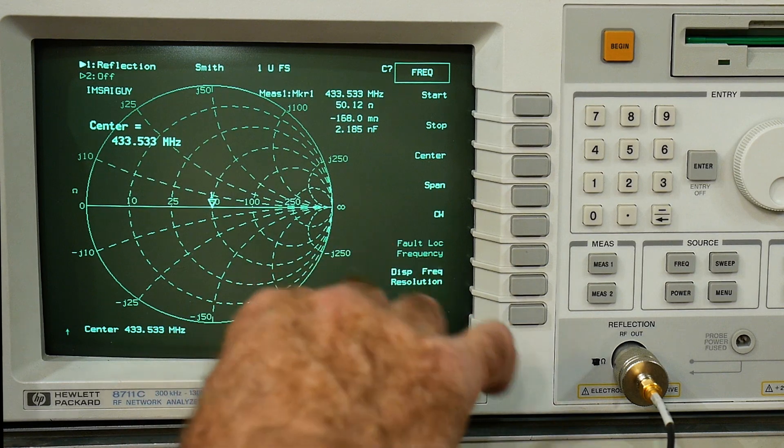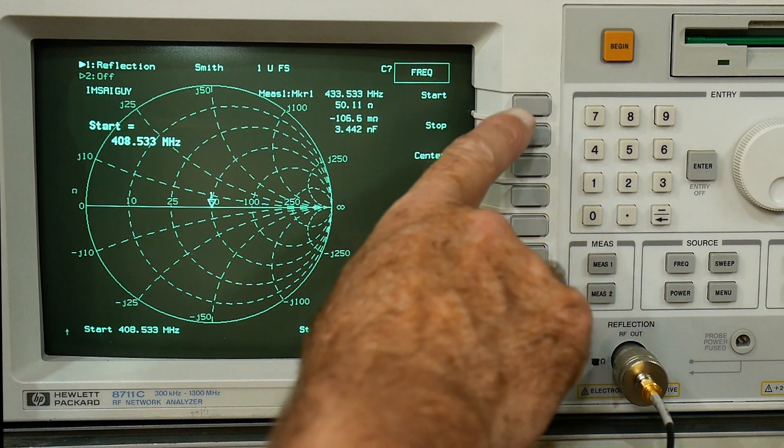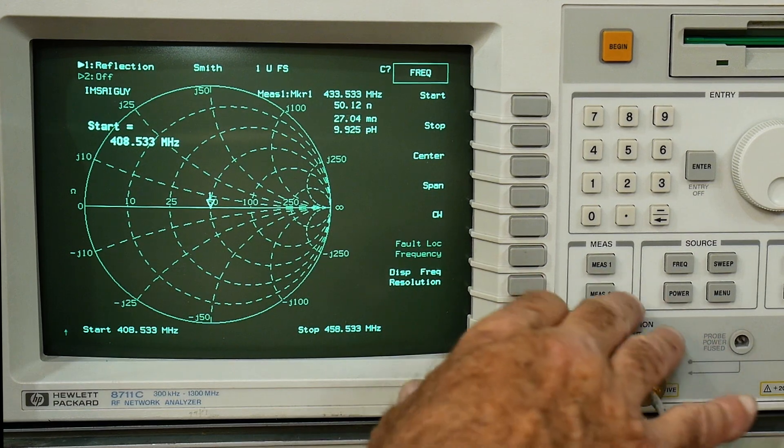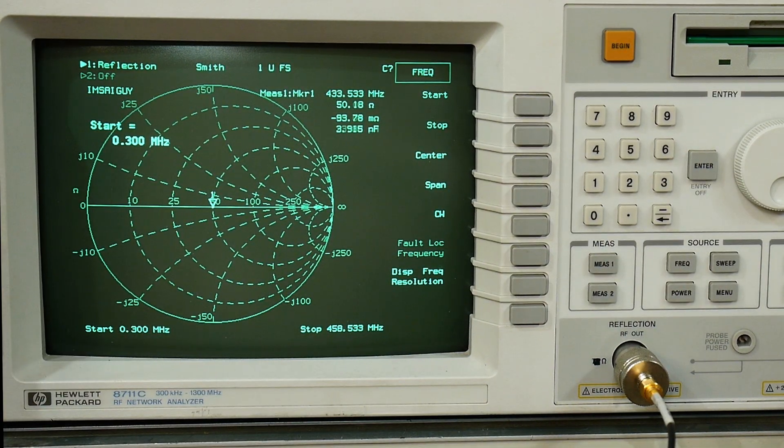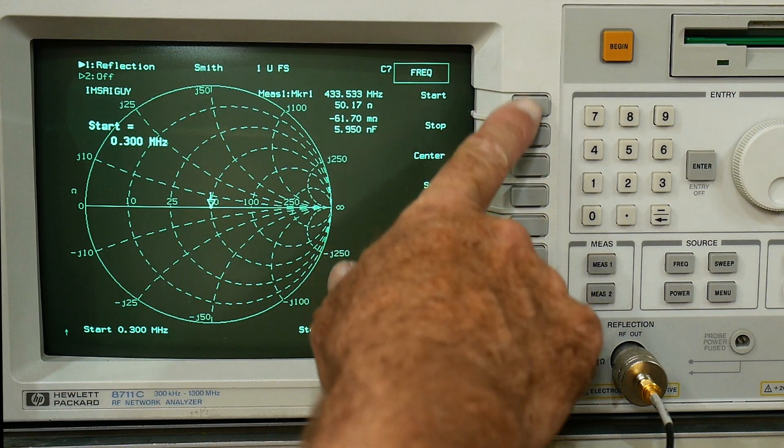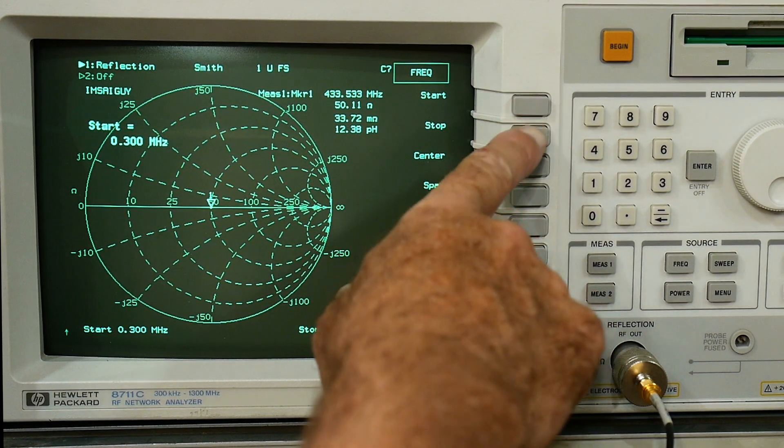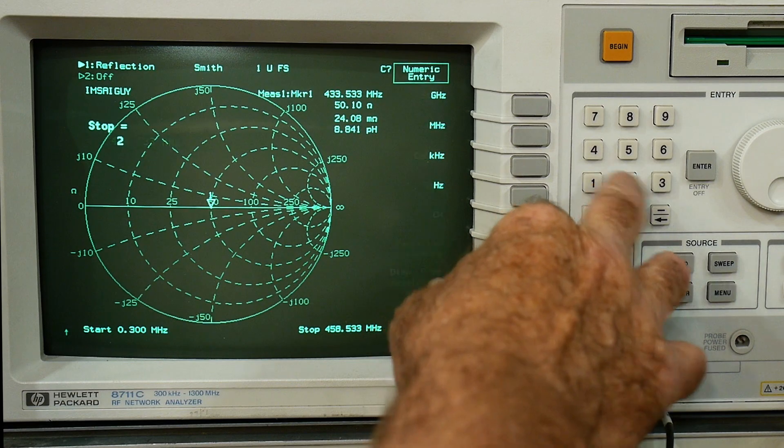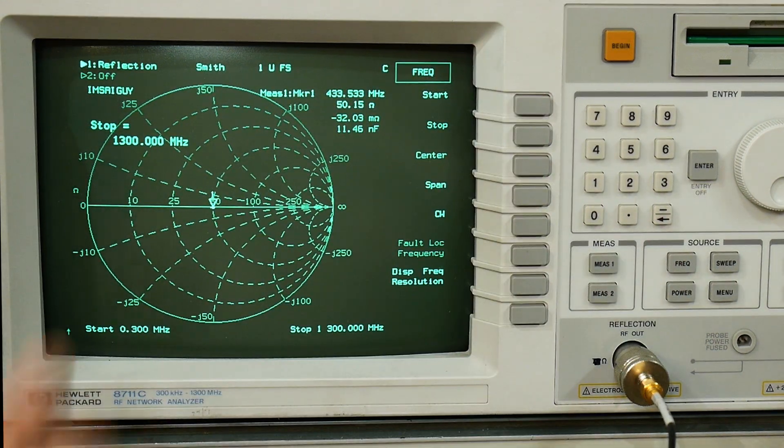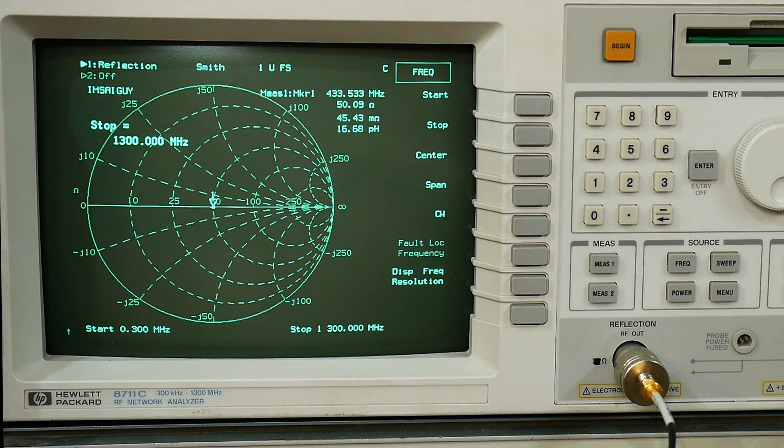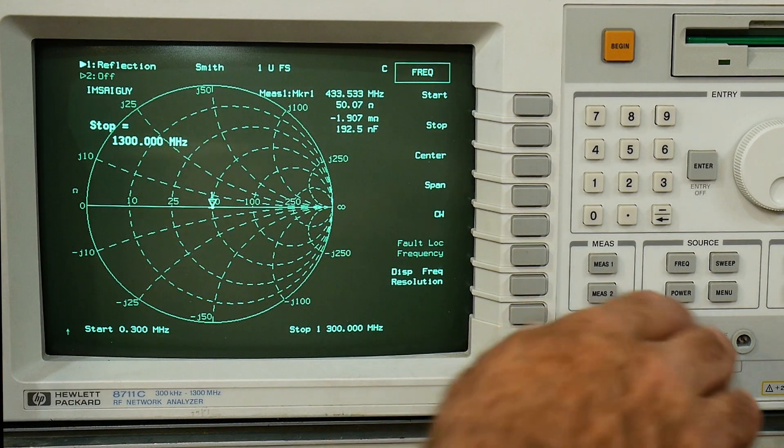The frequencies: you can do a start frequency of 0.300 megahertz is as low as it goes and we'll do a stop frequency. It's 1.3 so it goes from 0.3 to 1.3, 0.3 megahertz to 1.3 gigahertz. So that's its range.